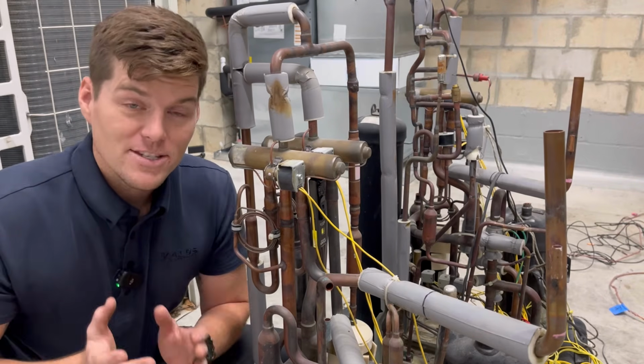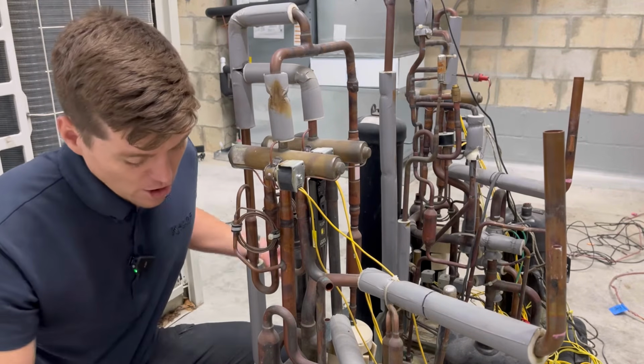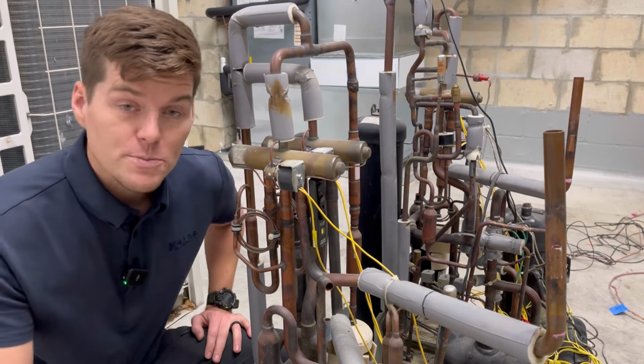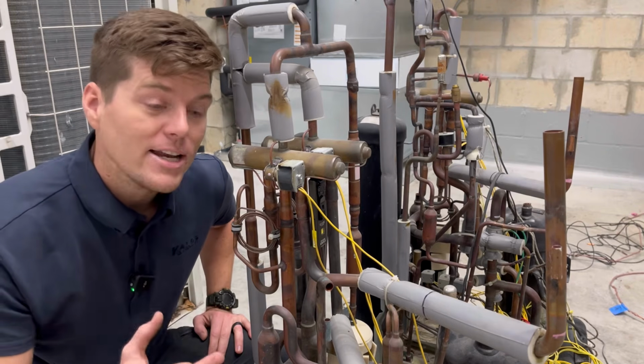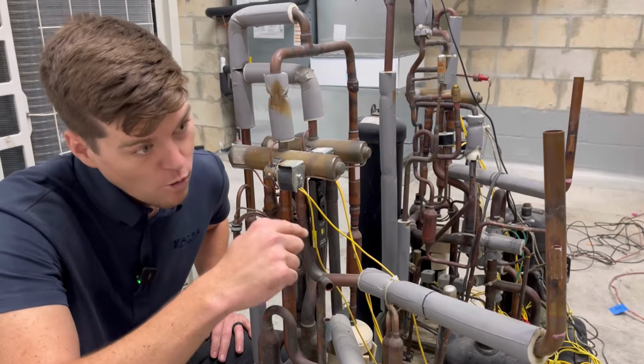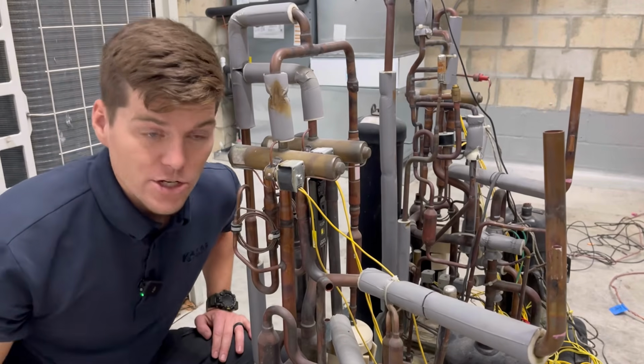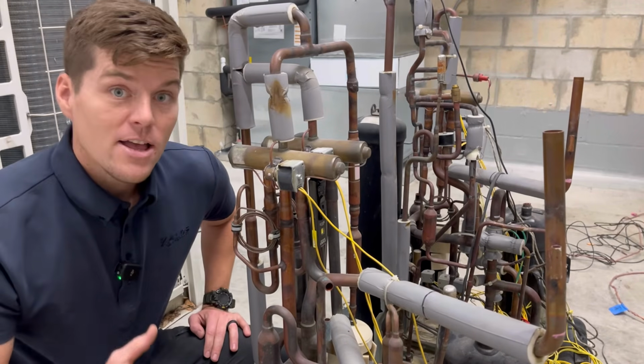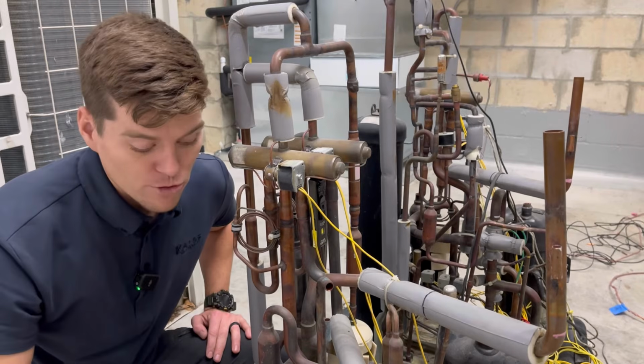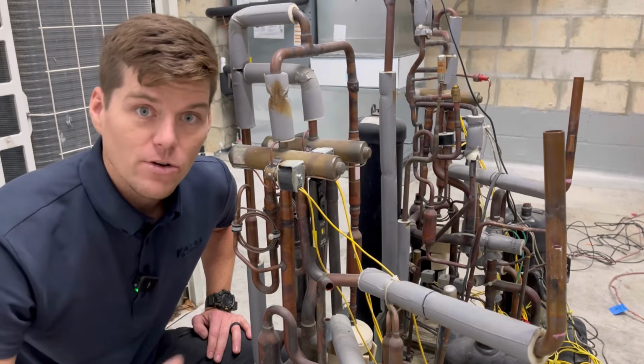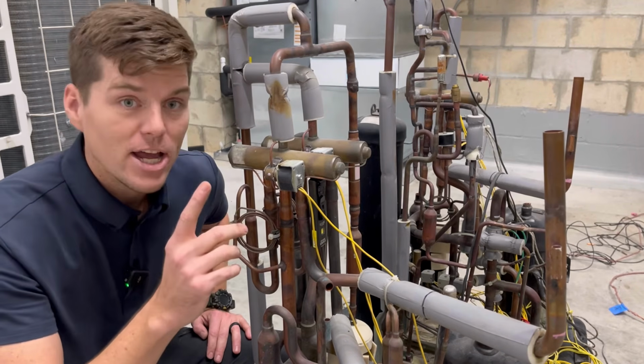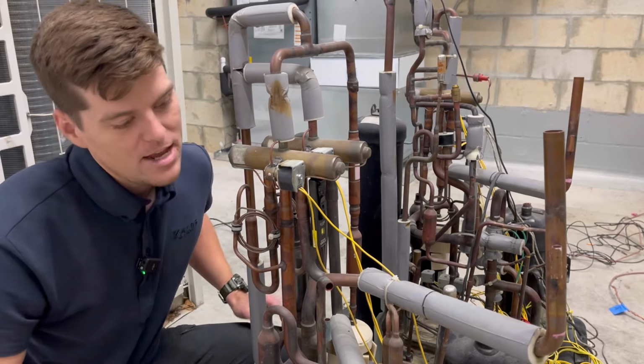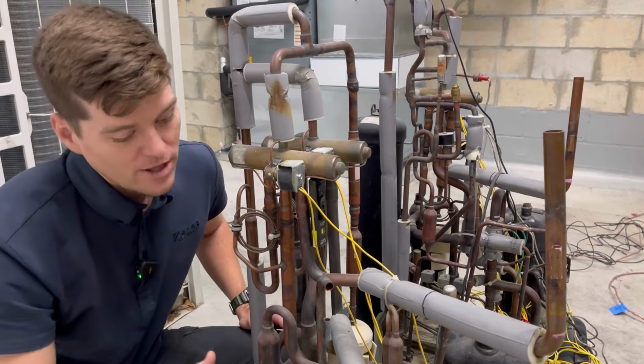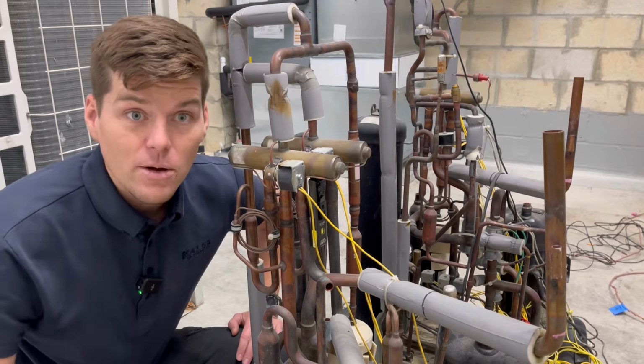Now, if I think about the science behind this, and I know that my system is in a 100% cooling state, that means that there should be hot gas going from here over to my actual outdoor heat exchanger. Now the question is, that is what I know to be true for cooling, so whether it's on or off, I don't care anymore. Now what I want to do is check, is the position correct? Now you can see if the temperature on this line to the outdoor heat exchanger is hot, okay, well then I know that it's shifted.